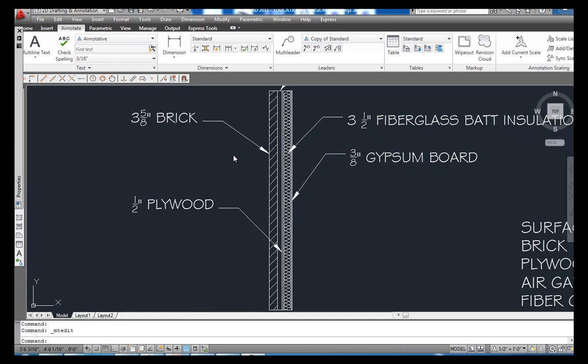Go to table 5.3, and it has a lot of commonly used building materials and their P-values. Now what a P-value is, is it shows you how much R-Value there is per one inch of that material. For instance, you have a material whose P-value is one and the material is let's say five inches thick, well that material's R-Value would be five because it's five inches thick times one. So now it's five inches thick, you just take that five times it by one and you get five. That's the difference between P-value and R-Value.